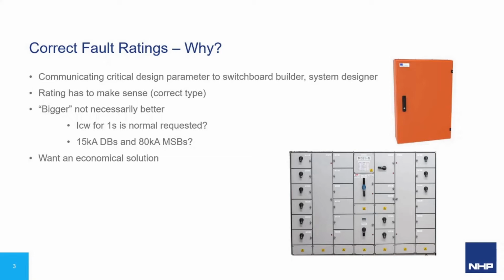ICW for 1 second is normally requested, but why? 15 kA DBs and 80 kA main switchboards, where do these ratings come from? At the end of the day, having a sound understanding of what fault levels are available and most appropriate will lead to the most economical solution.